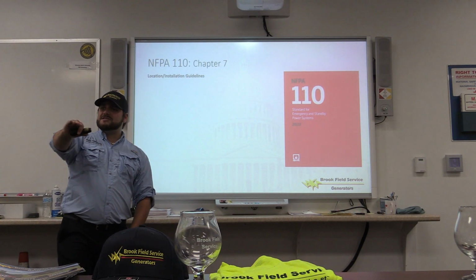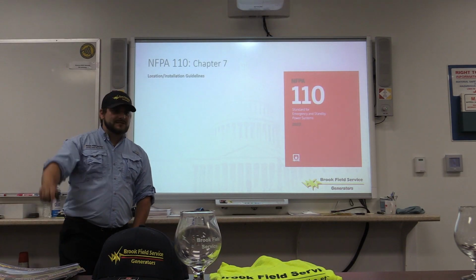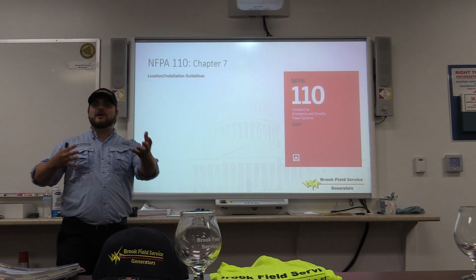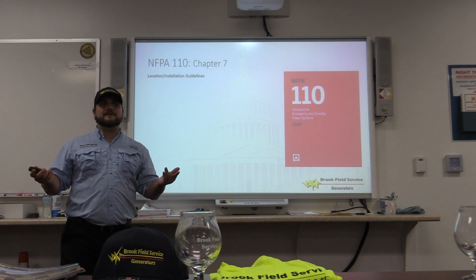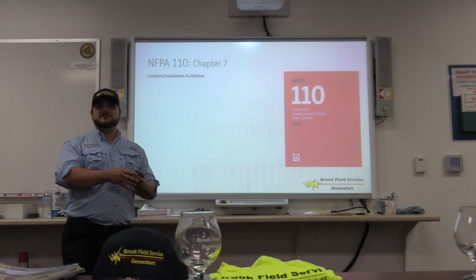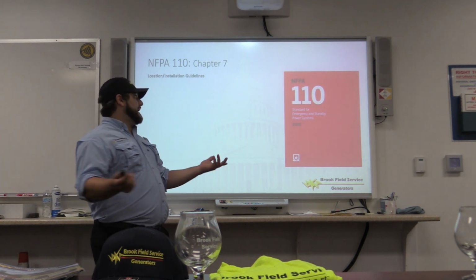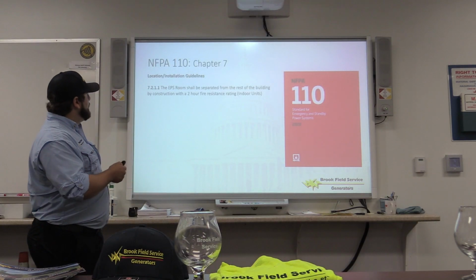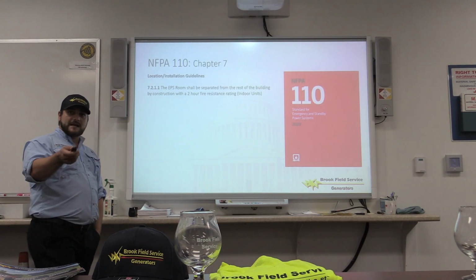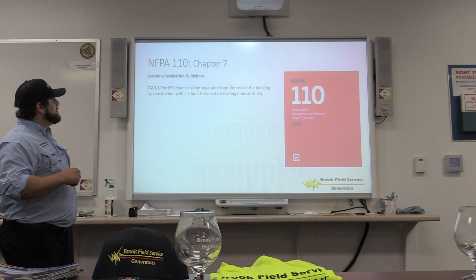We don't go too much into that. Alice and I talked a little bit about it because it's part of the turnkey care you're going to receive, at least from us, but other generator systems companies should take care of all this with a site review. But things to keep in mind that I've seen a lot, and Josh has too, the emergency power supply room shall be separated from the rest of the building by construction with a 2-hour fire resistant rating.